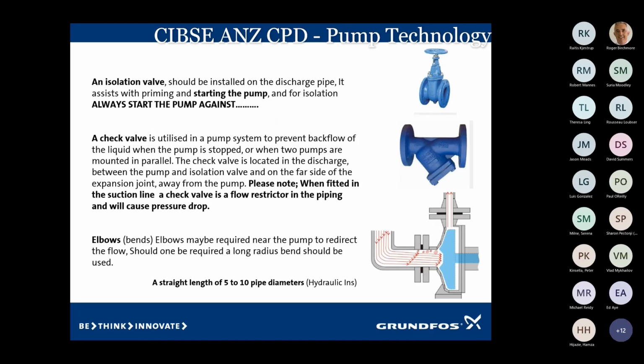And the diagram at the bottom there is actually showing a 90-degree bend, and you can see what's actually going on. It's forcing the water down. It's pushing the water onto the pump, and trying to force the impeller down. Again, it's just stressing right down through to the rest of the motor.